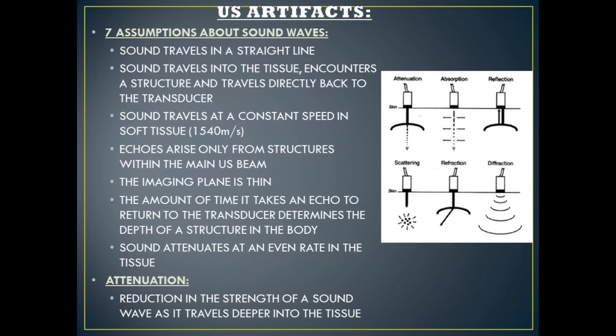An ultrasound machine makes seven assumptions about sound waves. Number one, sound travels in a straight line. Number two, sound travels into the tissue, encounters a structure, and travels directly back to the transducer. Number three, sound travels at a constant speed in soft tissue: 1540 meters per second.